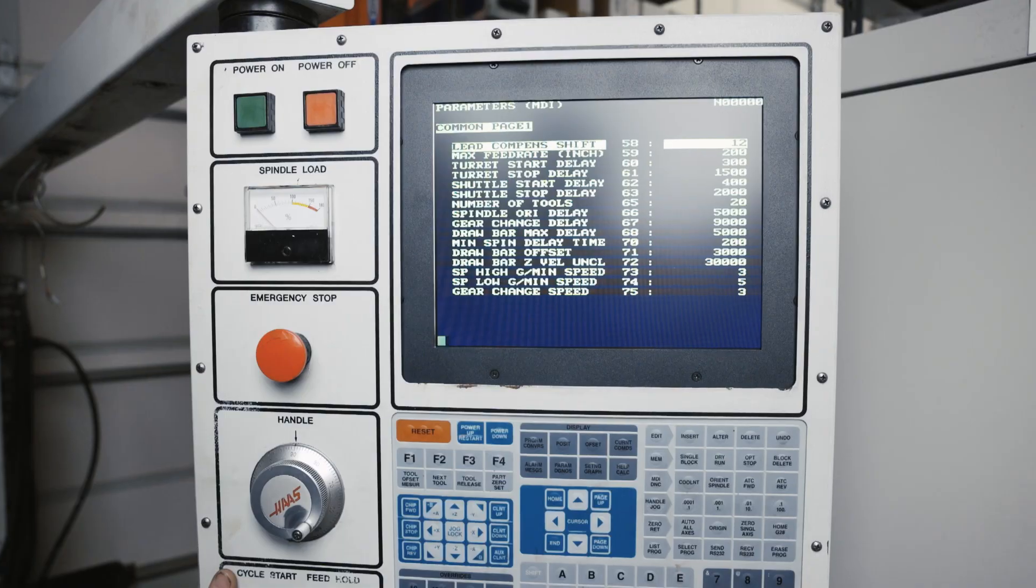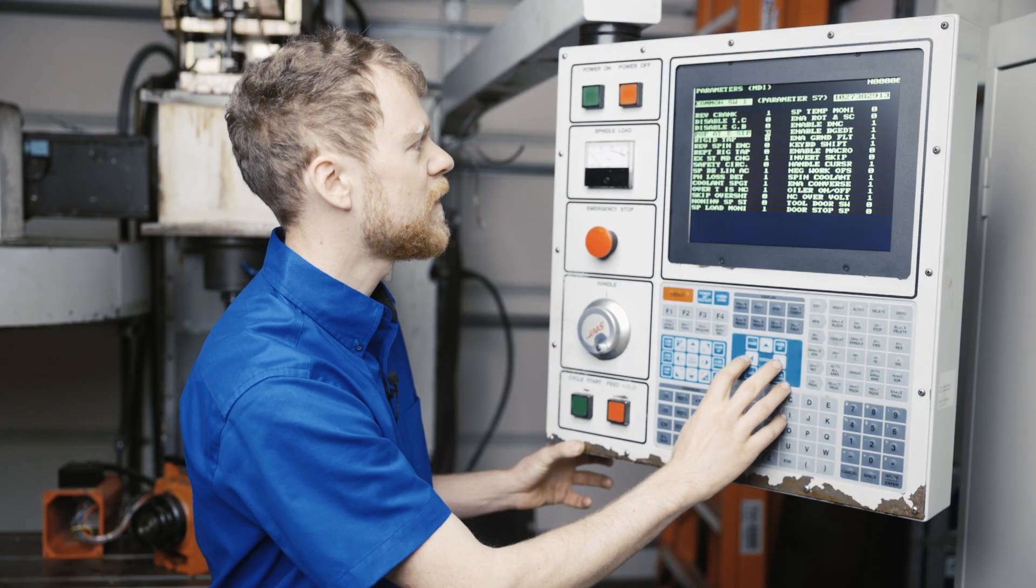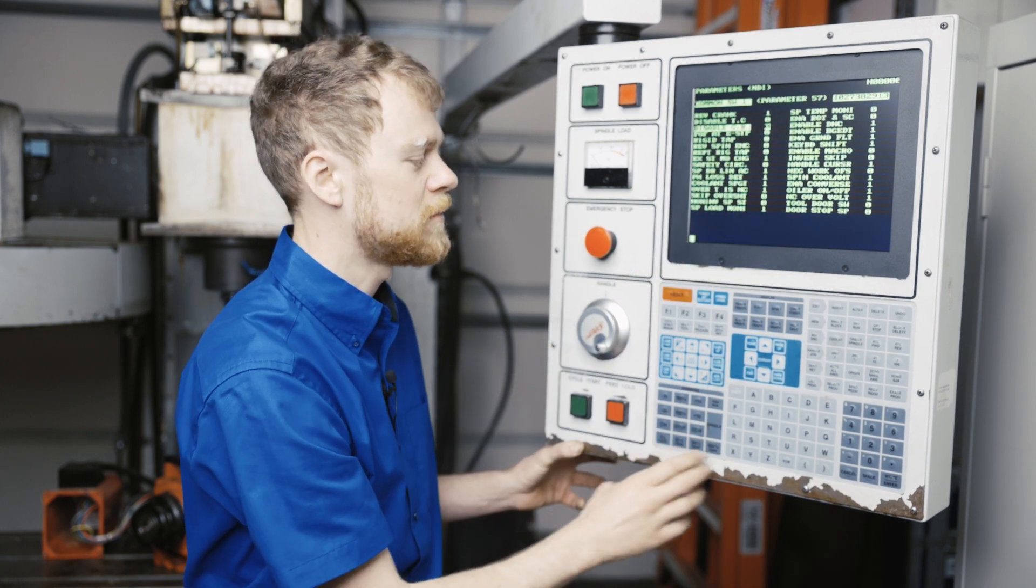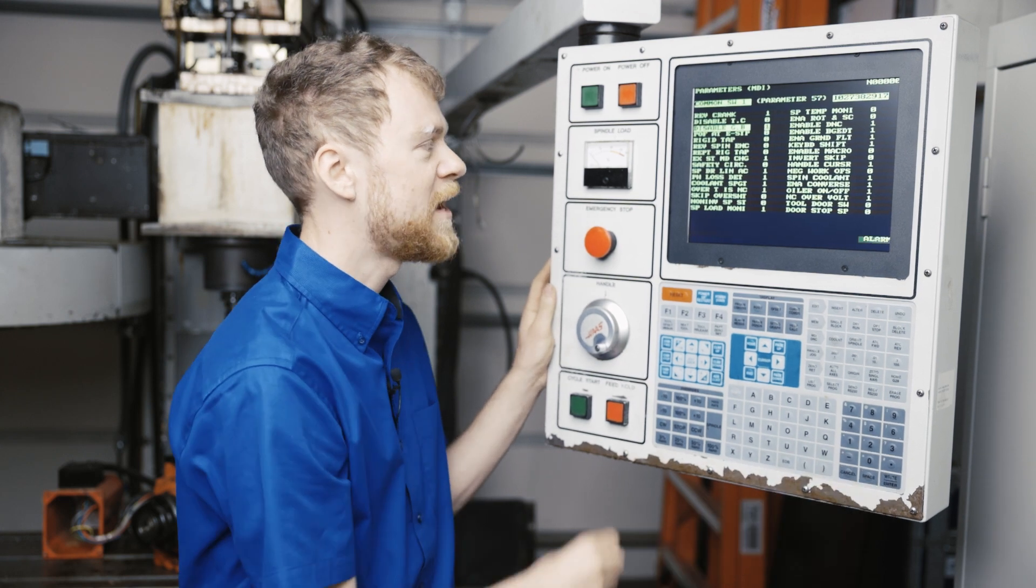Now we're going to go to parameter 57, press the down arrow key. You can use the left and right arrow keys to go to the third bit down from the top where it says disable gearbox. E-stop must be pressed in. Press the number 1 and press enter.